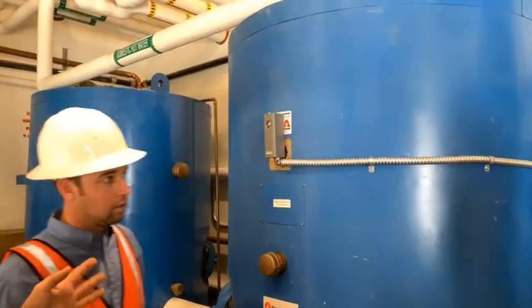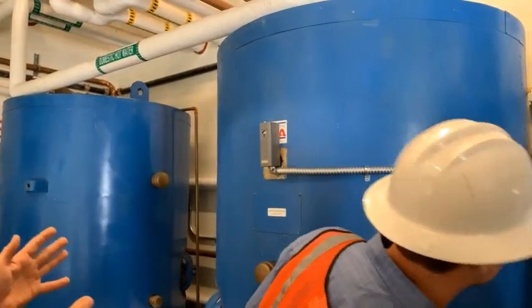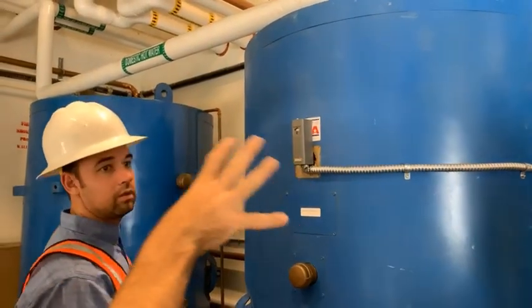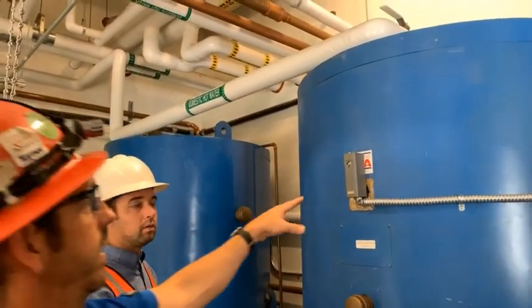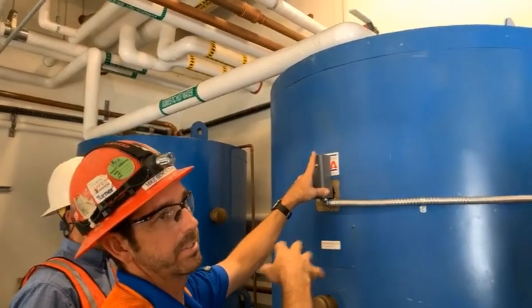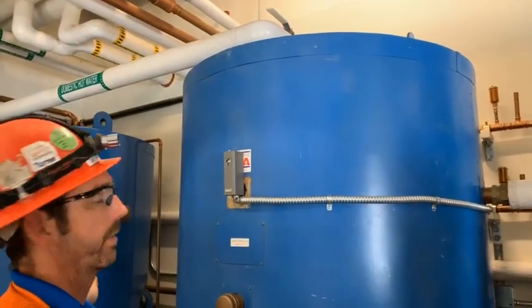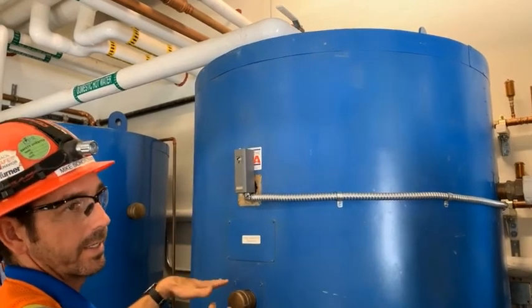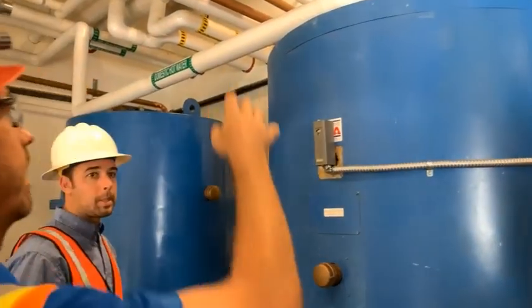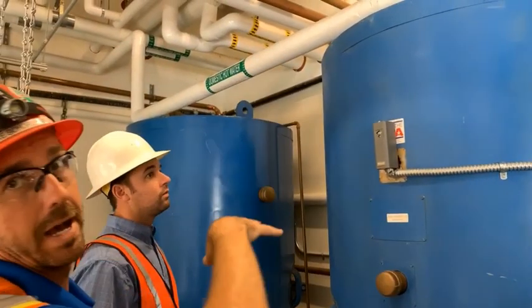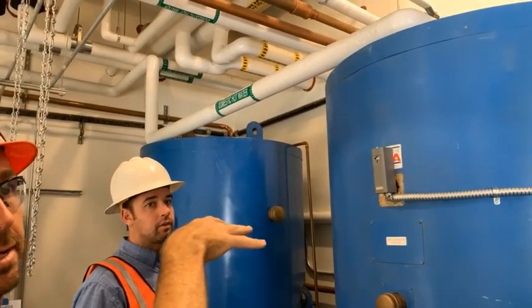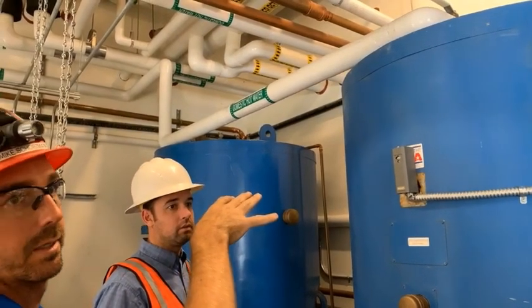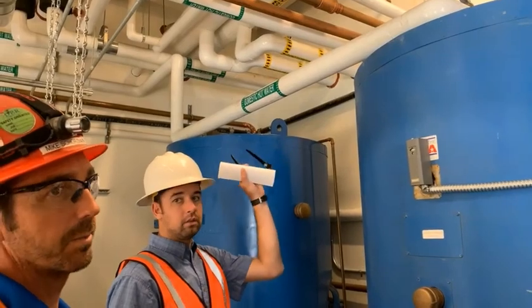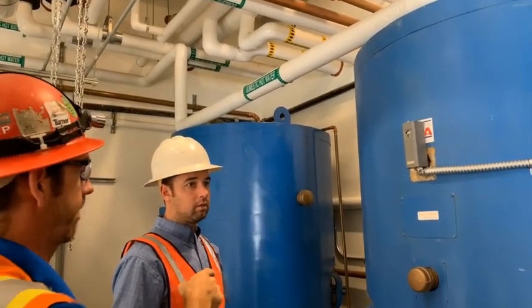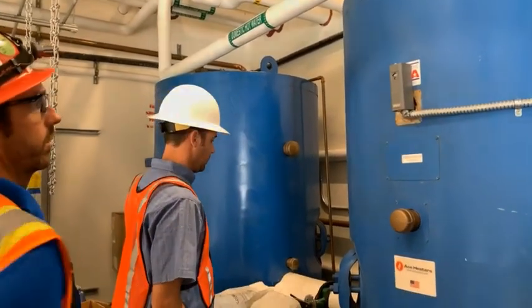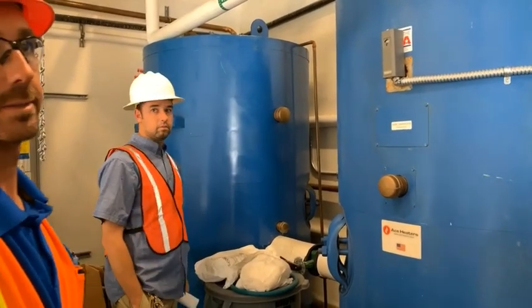The worst case scenario, if you only isolate one tank: if you drain this tank while the pump's running, it'll just keep that pump running, but it'll always cycle water into the opposite tank because all the piping is tied together. If you have to isolate both, you have to turn the pumps off. If you do have to work on this tank, remember how many valves there are to isolate a tank? 3. Plus the isolator valve, because you have to isolate the tank with the middle. So there would be 3 plus the isolator valve.